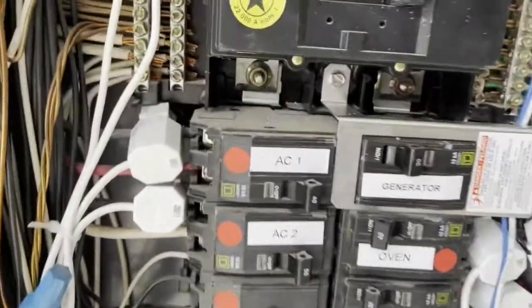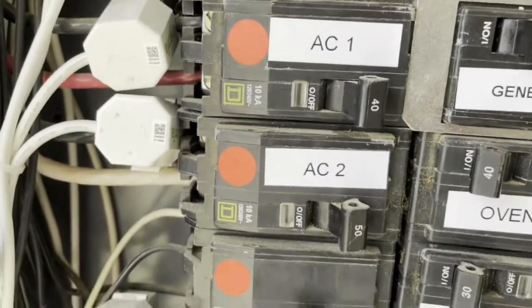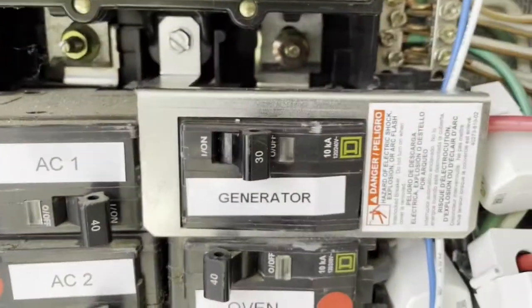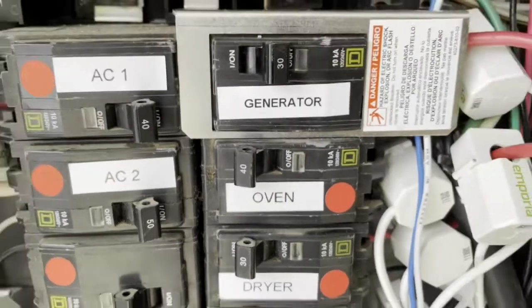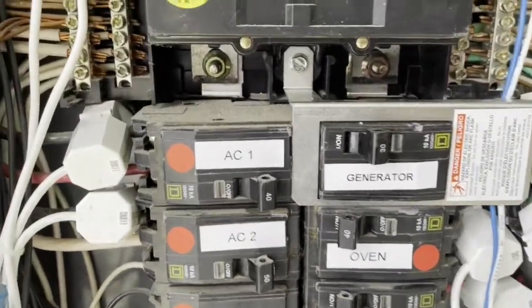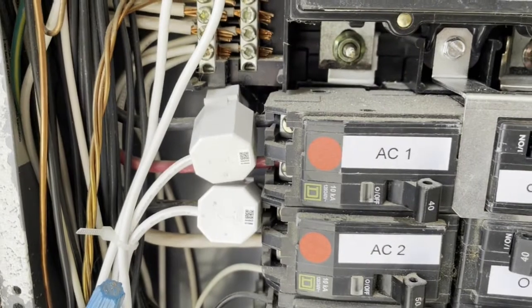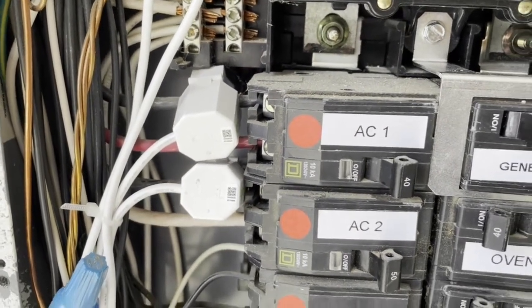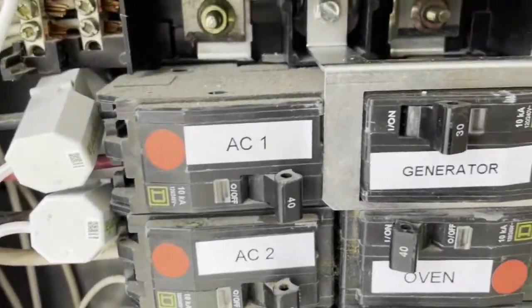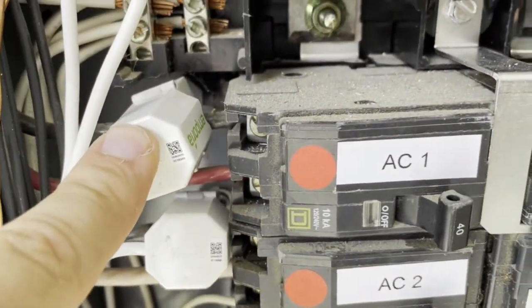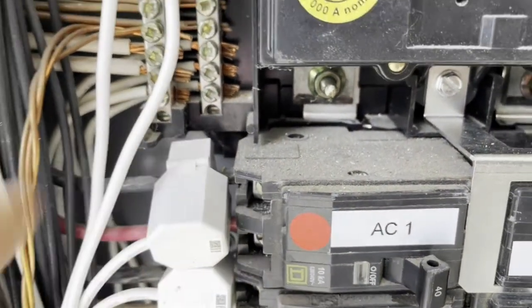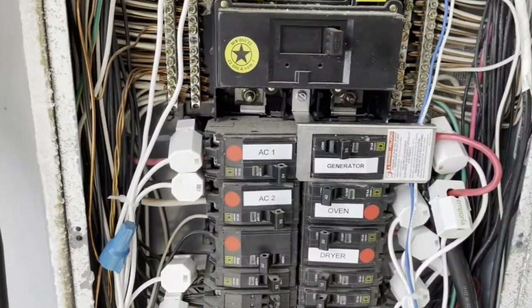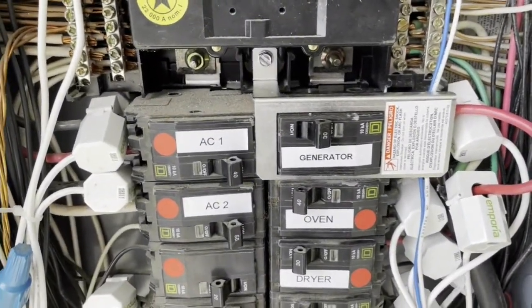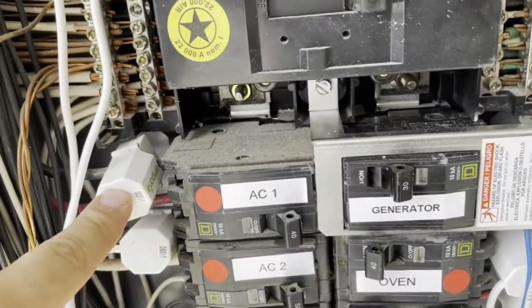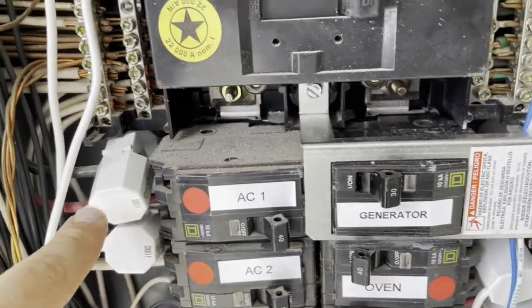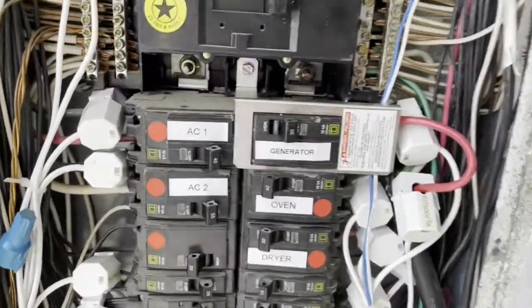Here's the trick: AC1, AC2, these are all 240 circuits, same for the oven and dryer. But these are balanced loads, meaning if you have current in one phase, the current in the other phase will be almost equal. So you don't need to clamp two sensors, just clamp one, and in the app there's a multiplier so you multiply it by 2. If one sensor shows this much power, your total consumption is double that.